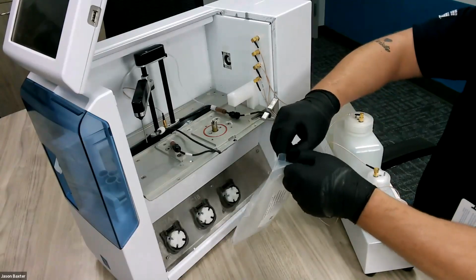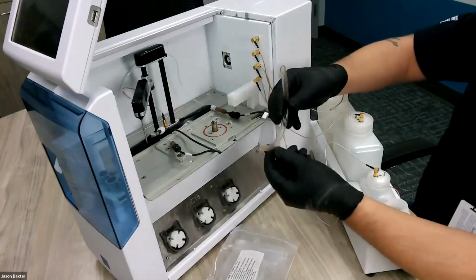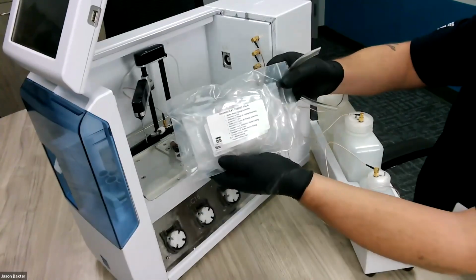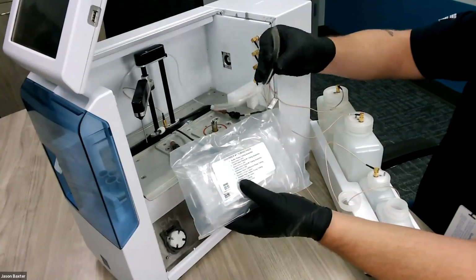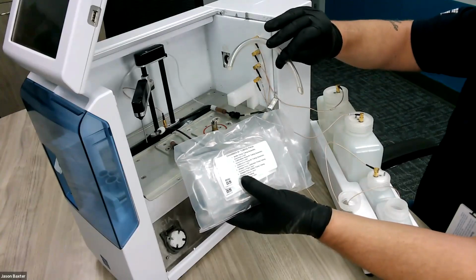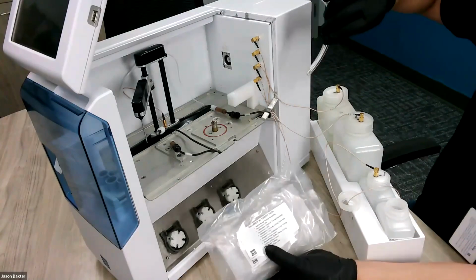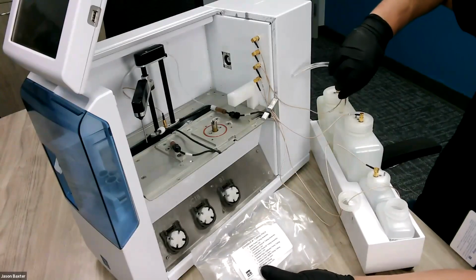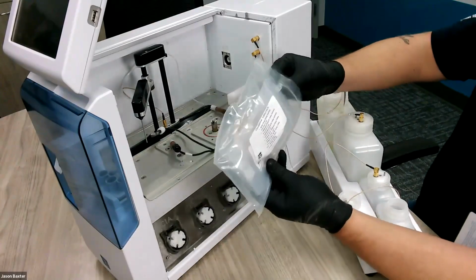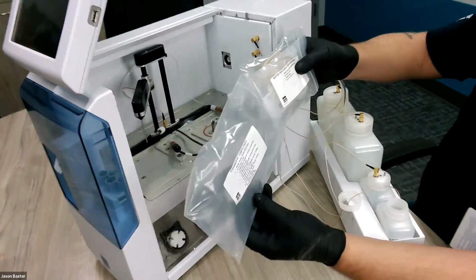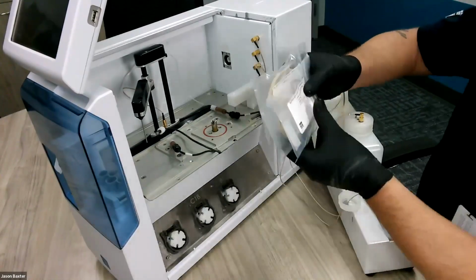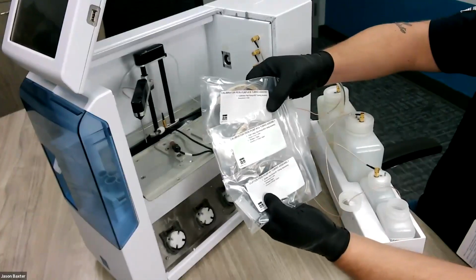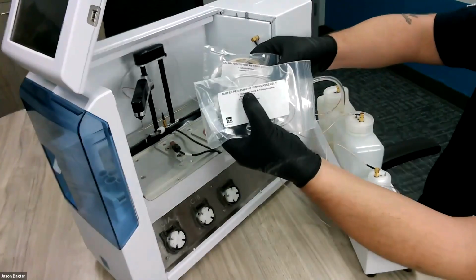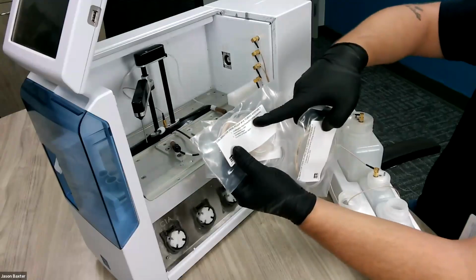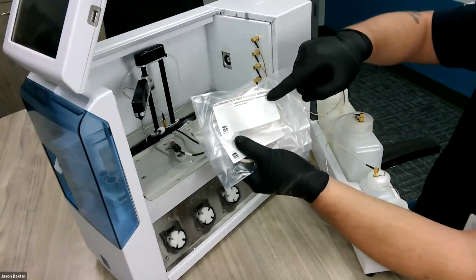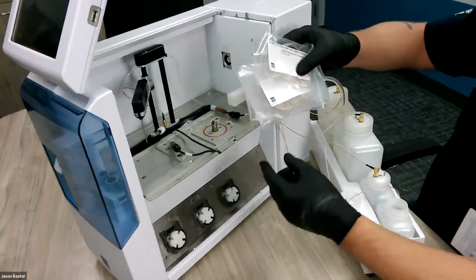So here we go, the meat and potatoes, as we like to say, of this device. When you open up the chamber 1 tubing pack, you're going to have this one tubing that is not labeled. It's for your waste. It's very self-explanatory. I will usually take it and just install it straight into the waste bottle so I don't lose it. So inside of the large bag, aside from the waste tubing, we have 3 small bags: buffer pump number 1, calibrator pump 1A, calibrator pump 1B. So we have each one individually bagged.